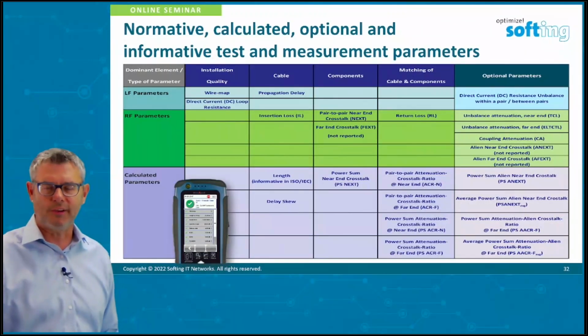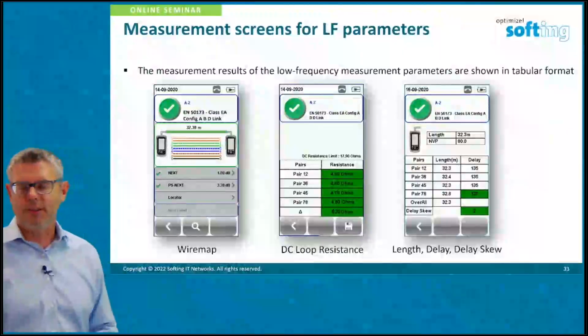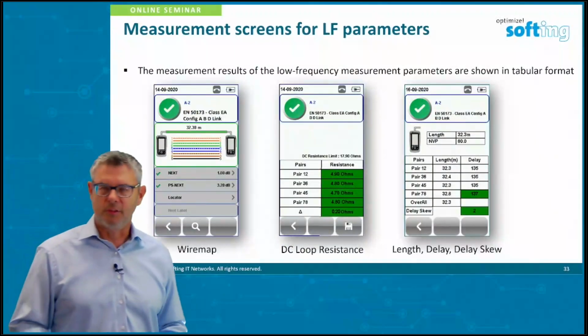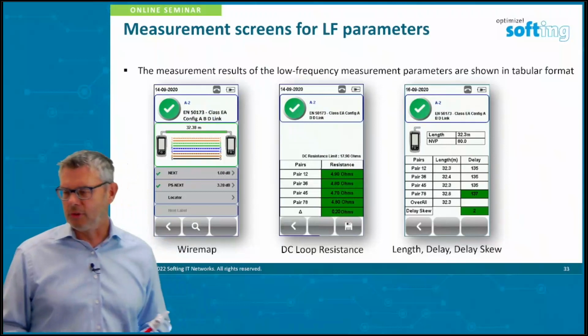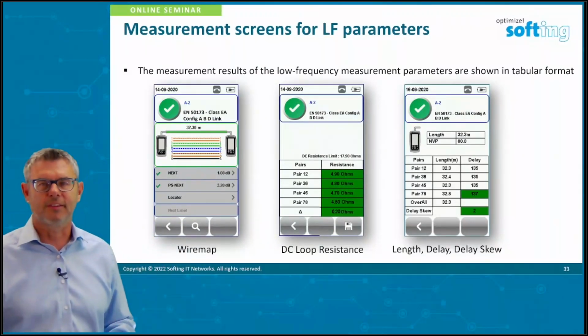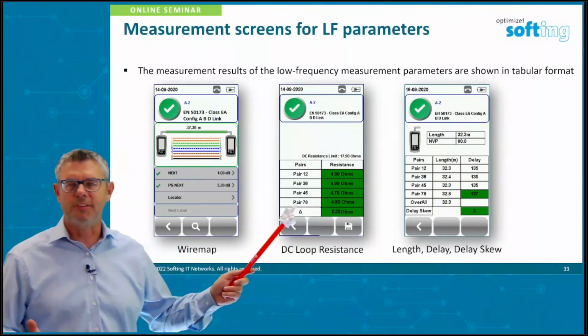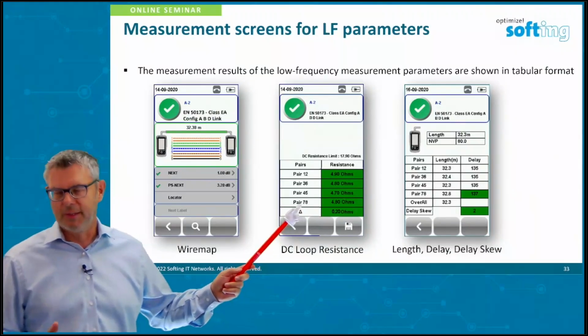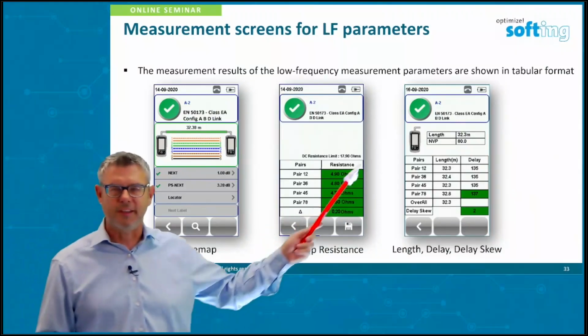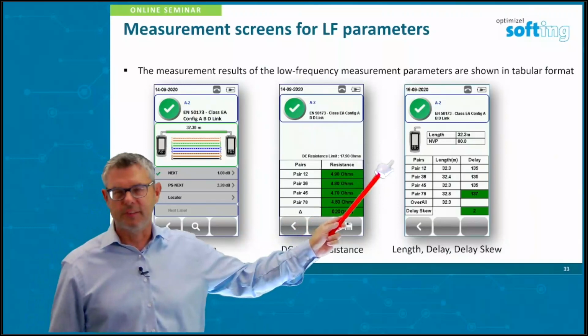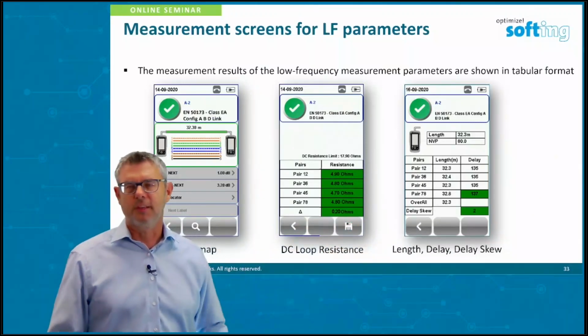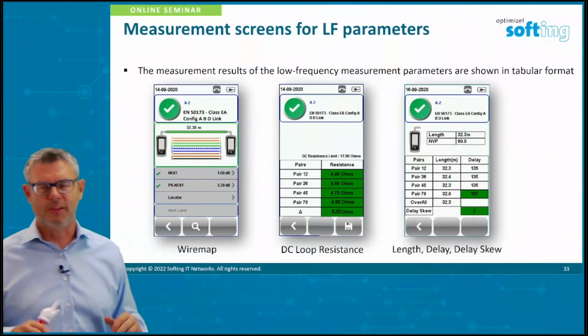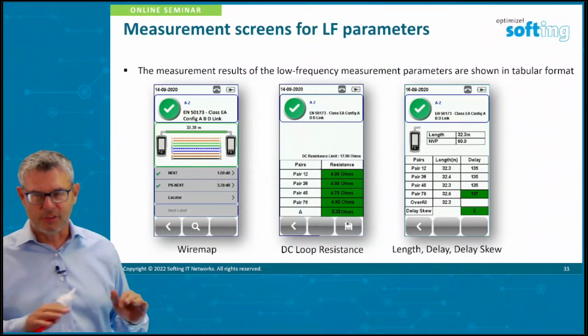So we're getting a few different result screens from the tester. The tester we're actually using is our WireXpert, of course. So you get the wire map screen, and you also get a summary screen, and tables for DC loop resistance, for example, and a table expressing the length values and expressing the delay and delay skew values. These are called the low frequency measurements, the low frequency LF measurements.